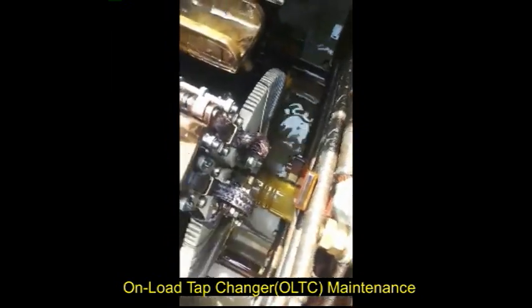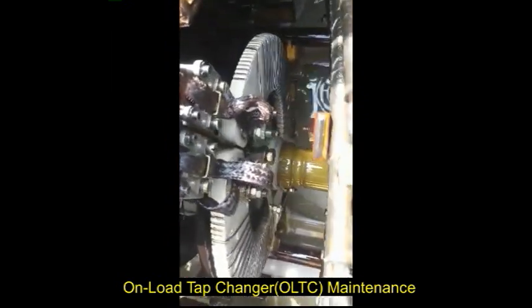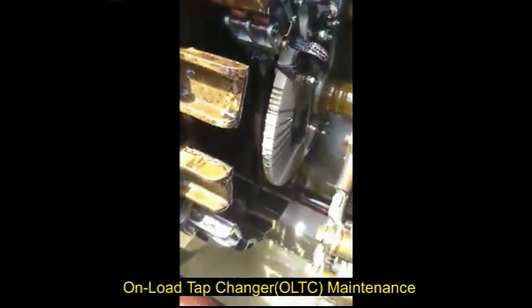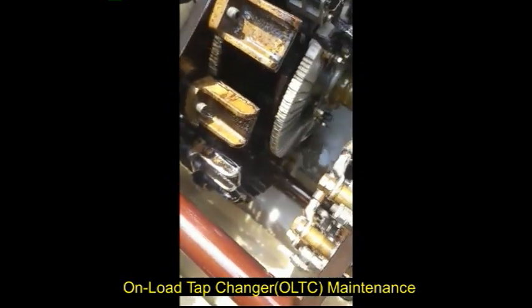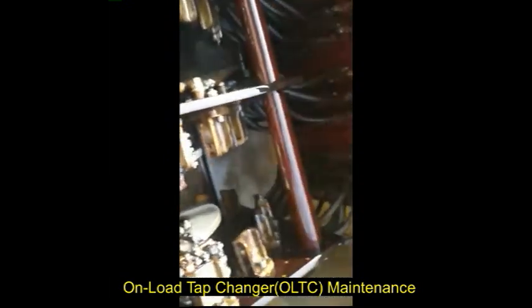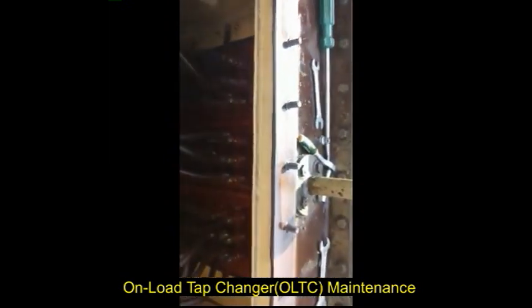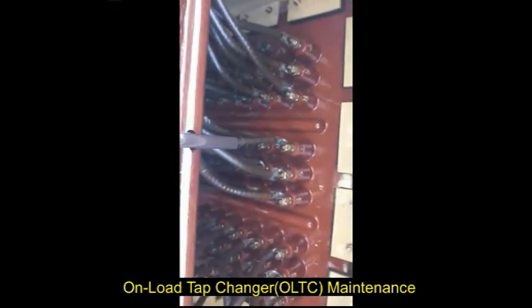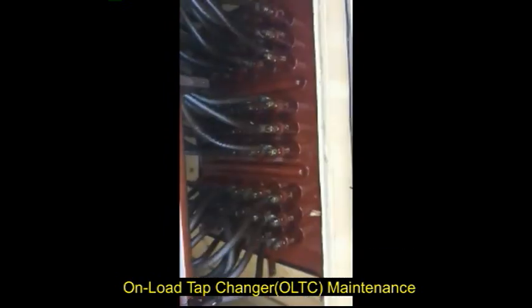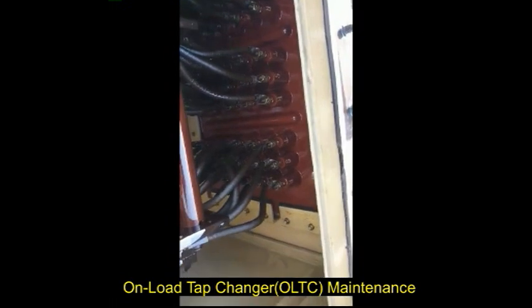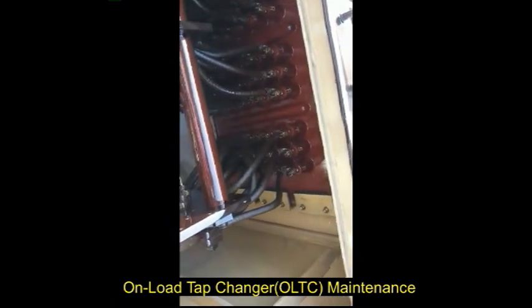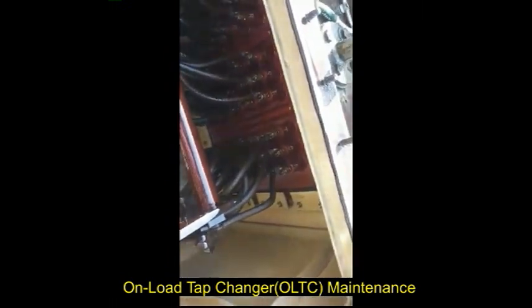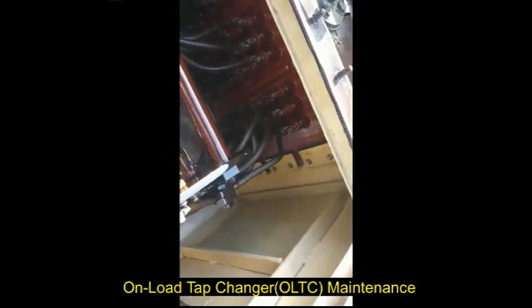These arcs tend to carbonize the switching oil, which in turn leads to corrosion of the internal components of the LTC. The intensity of the oil contamination due to these arcs generally depends on the number of operational hours, the operating current on the LTC, and, last but not least, the quality of the oil used for insulation purposes.